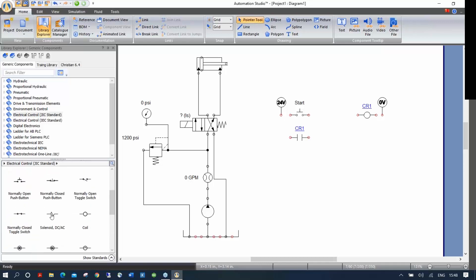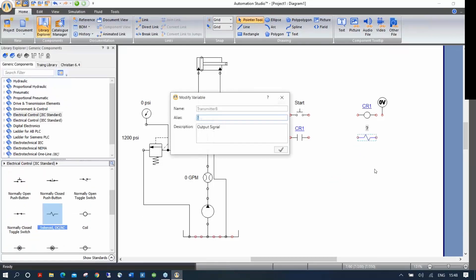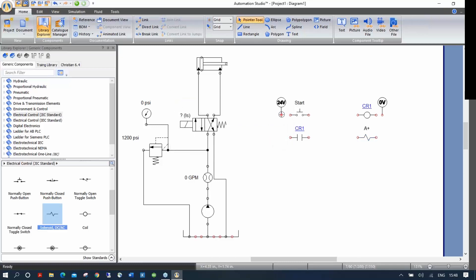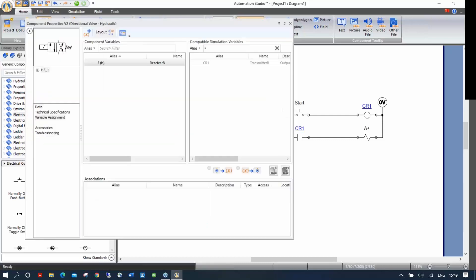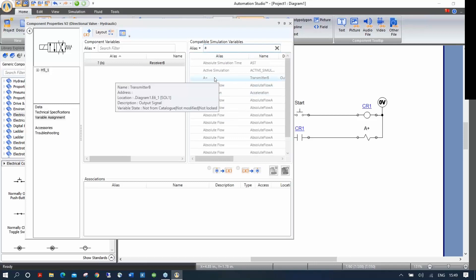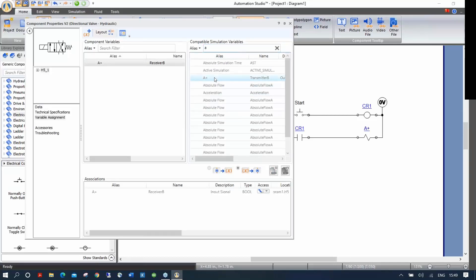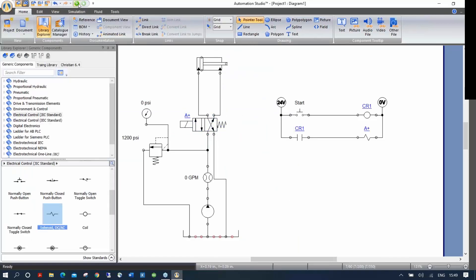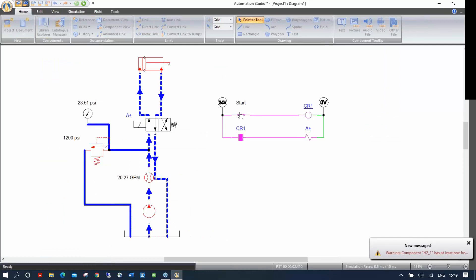I'll put a solenoid element in the circuit and call it A+, then connect the components together. I need to associate A+ with the hydraulic solenoid — double-click on it, filter for 'A,' find A+, click twice, and now the link is made between the electrical solenoid coil and the hydraulic directional valve. When I simulate again, I have a functioning electro-hydraulic circuit.